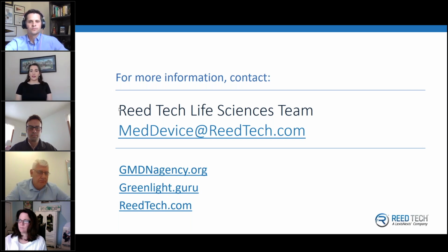So I think getting a good handle on those hierarchies and what they look like, what they feel like, what the options are is a good place to start. Yeah, and I would add, on the CE mark side, the MDR has an annex that is almost like a flow chart or a series of rules that asks, are we an invasive device or not, and it really walks you through the process to get to your classification. I know different people have different opinions on what's easier, FDA or CE mark. I think for identifying your class, the MDR lays it out pretty easily.